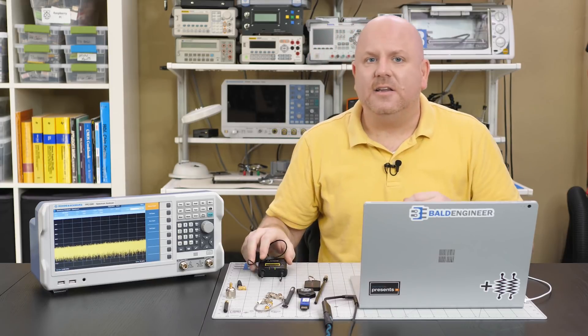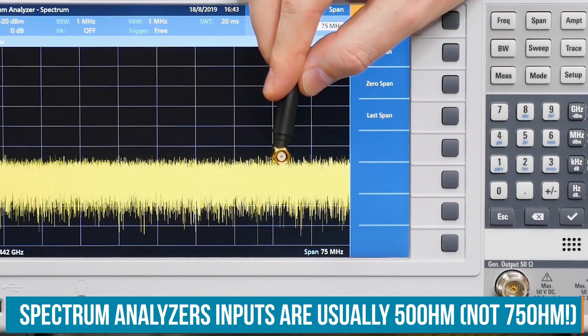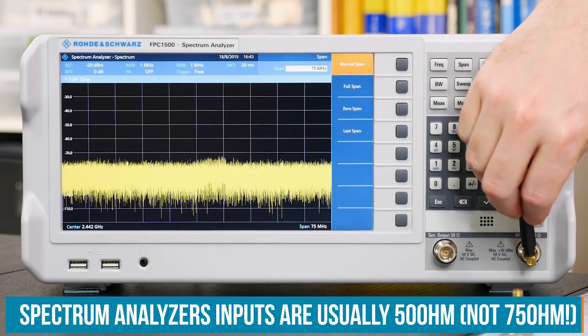Now, first, we need to get our signal into the analyzer. And usually, you would use cables to attach to the n-type connector. For our exercise, I'm using this small antenna. It has an SMA connector on it, which will not directly mate to the n-type connector. So, I'll have to use an adapter.